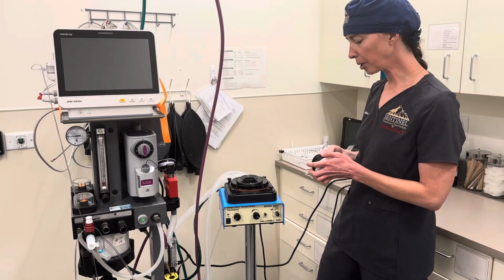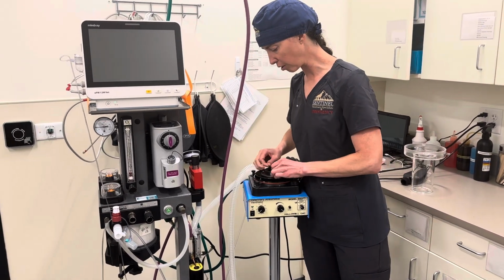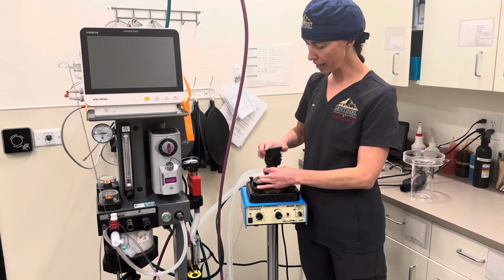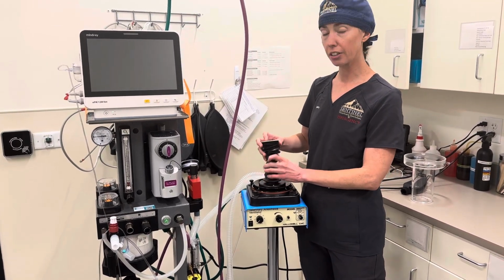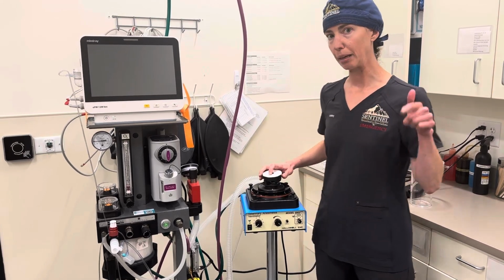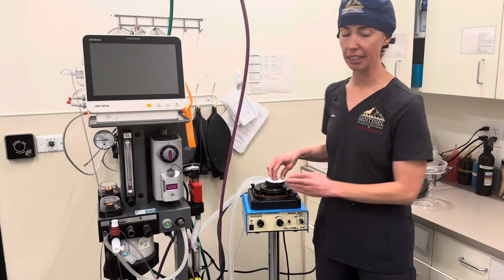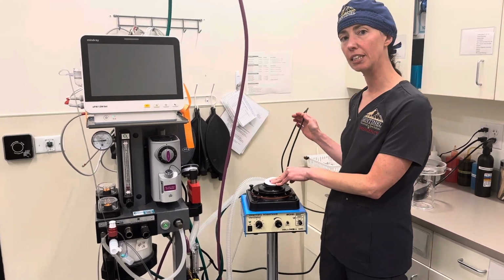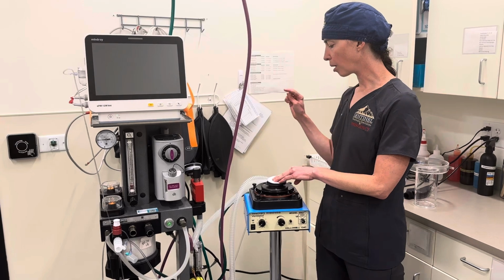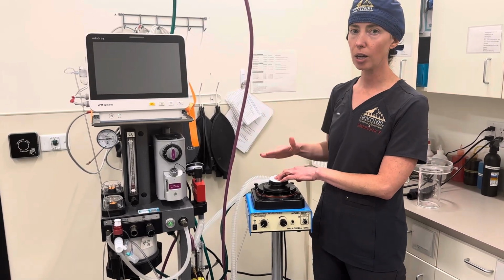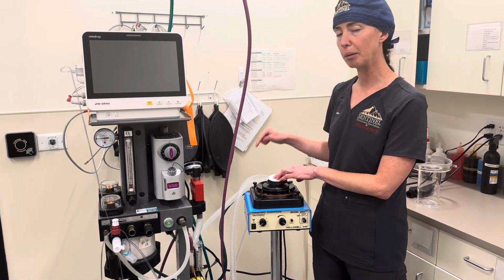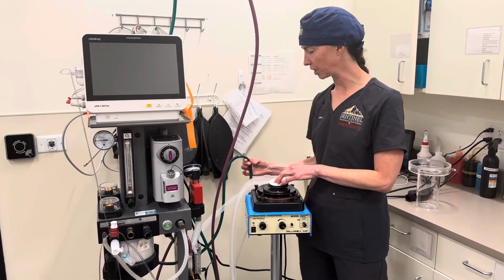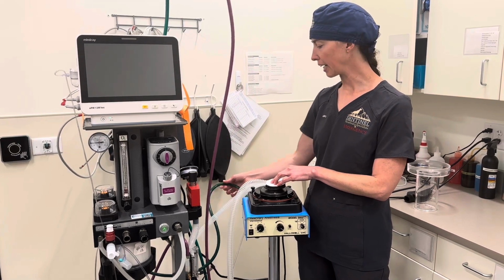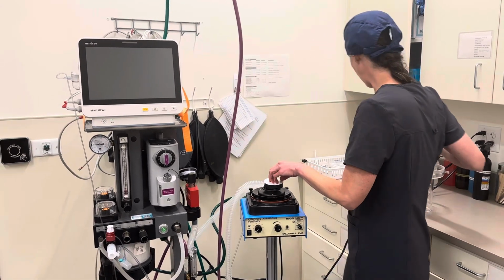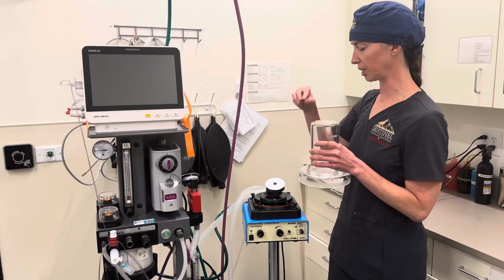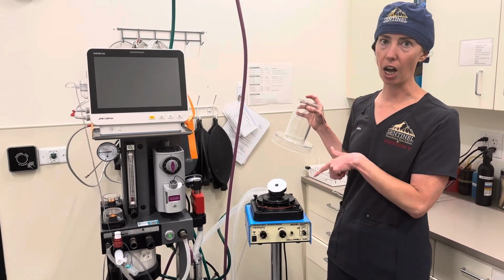So as far as setup goes for this machine, just the basics of what needs to be plugged into what: this particular ventilator needs to have electricity because of the time cycled component. And so we have it plugged in here behind me. You just have to make sure your power cord is plugged in. And then the firing of the bellows is by compressed oxygen. On the back of this machine, you'll see an oxygen line, and that is the gas that comes into the machine that fires into this acrylic piece and pushes the bellows down. So you need to make sure it's hooked up to oxygen.